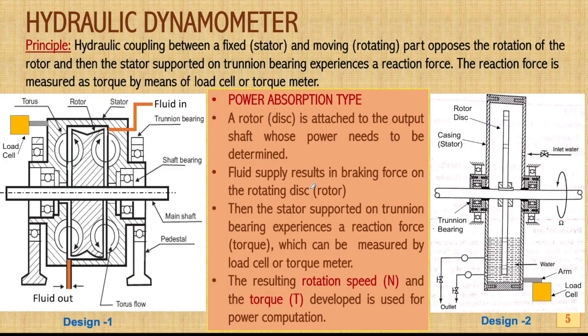Another kind is the hydraulic dynamometer. The principle is hydraulic coupling between a fixed member called the stator and a moving element — a disc or rotor. The coupling between stator and rotor opposes the rotation of the rotor. The stator supported on trunnion bearing experiences a reaction force, which is measured as torque by means of a load cell or torque meter.